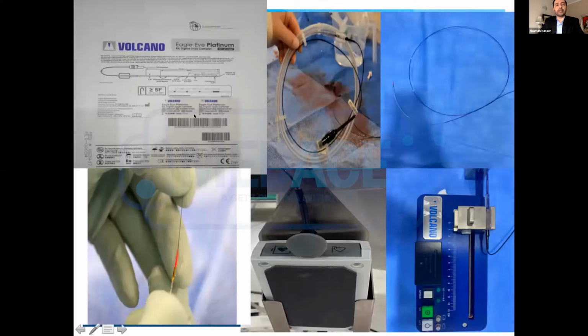This is the package insert of the Volcano catheter, with the same diagram over here. This is how it comes out of the packet. It's literally plug and play. You just plug it into the transducer over here, and the console is on the side, and you're ready to image. You advance it over the wire like a regular monorail balloon. For an automated pullback, you insert this back end into this, and you can set the speed over here, and it will do an automated pullback. It's a very simple assembly and literally takes a few minutes to get started and take the images.